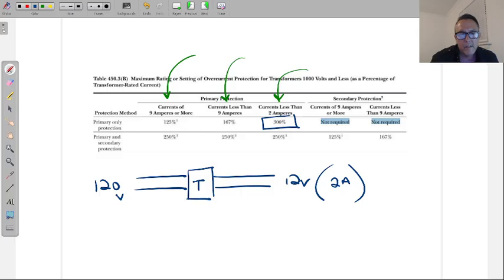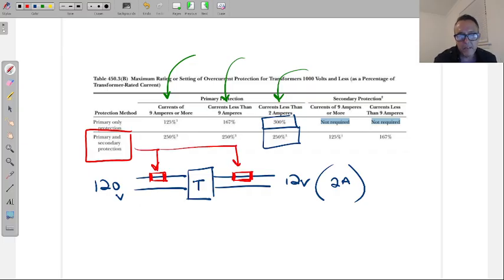The breaker or fuse, if you're going to put one, and again, you don't have to worry too deep about primary only protection or primary and secondary protection. It does change the numbers here, meaning if you're going to put a fuse, let's say for example, on the hot, on the primary side, you wouldn't put it on the neutral. The neutral does not need a fuse. And you're going to put a little fuse on the secondary side of the transformer. Now you're doing this one. In other words, primary and secondary have protection, right? Primary has, secondary has.